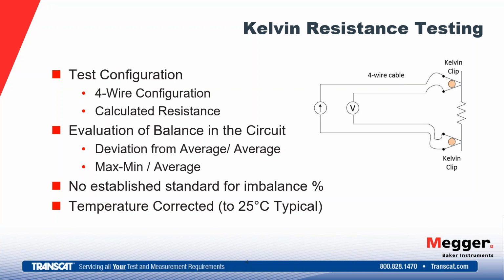We're also going to take our temperature, and the resistance that we measure, we're going to temperature correct it, because as temperature increases, so does the copper resistance. So if we want to trend over time, then we're going to need to temperature correct. Typically that's at 25 degrees C. I have seen some places that will use 20 degrees C for that correction factor, or the temperature that we're correcting to. It doesn't matter whether it's 20 or 25, you want to be consistent in that measurement so you can trend over time to see how that trend is going as you progress through the testing.